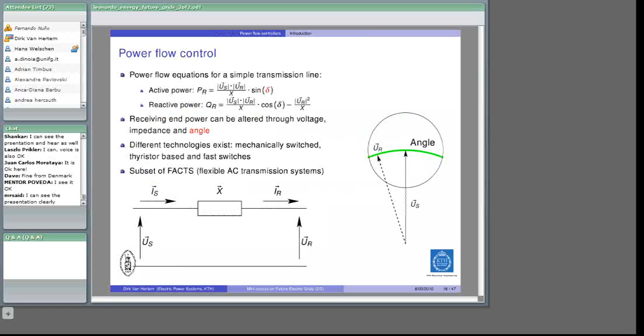Some examples: a phase shifting transformer, which is a mechanically switched device. It's basically just a transformer, or sometimes two transformers. The basic principle is that it injects part of the line voltage. If you have the phasor voltage of phase 1, you inject a perpendicular voltage of that line voltage in series, transforming part of it, and the effect is that you push the voltage between sending and receiving side apart from each other. There are different types, but most importantly it's relatively cheap, robust, efficient, and slow.